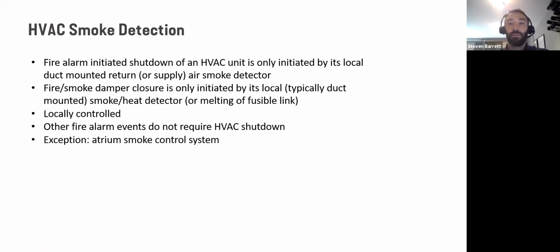And then the big exception here, and the segue to this last section, is an atrium smoke control system actually might require you to take some HVAC action of either turning on the smoke exhaust fans or shutting dampers along the atrium boundary. So we will get into that section next.